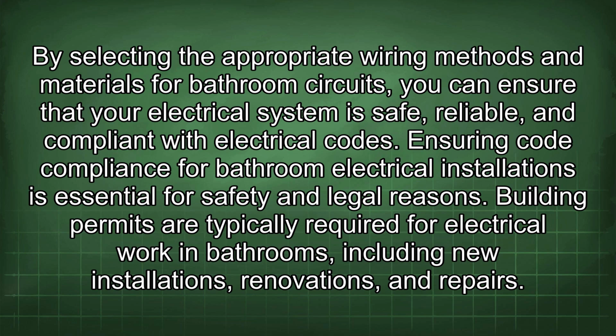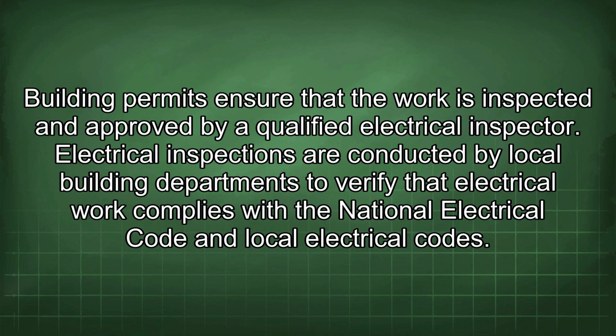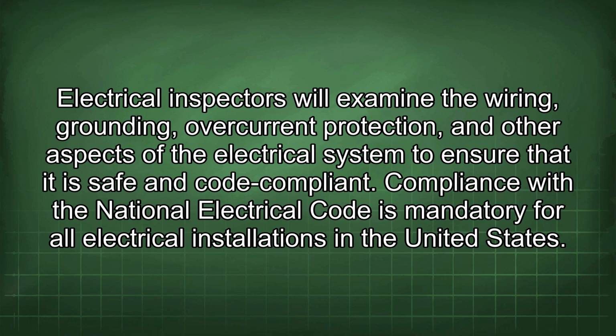Ensuring code compliance for bathroom electrical installations is essential for safety and legal reasons. Building permits are typically required for electrical work in bathrooms, including new installations, renovations, and repairs. Building permits ensure that the work is inspected and approved by a qualified electrical inspector. Electrical inspections are conducted by local building departments to verify that electrical work complies with the National Electrical Code and local electrical codes. Electrical inspectors will examine the wiring, grounding, overcurrent protection, and other aspects of the electrical system to ensure that it is safe and code compliant.